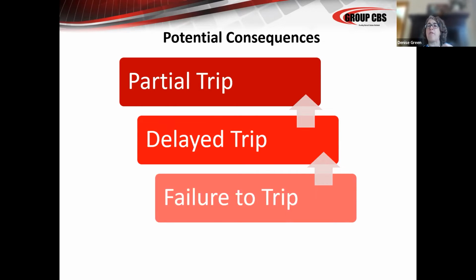The first problem with lack of maintenance is your breaker just doesn't trip. So the problem with the failure to trip situation is you can overstress the cables and the bus longer than the equipment was designed to be stressed for. And if your breaker doesn't trip, hopefully the breaker upstream or the fuses or the device upstream is the thing that does trip. But the consequence with that is you have a larger outage. You didn't anticipate that all of that was going to happen.